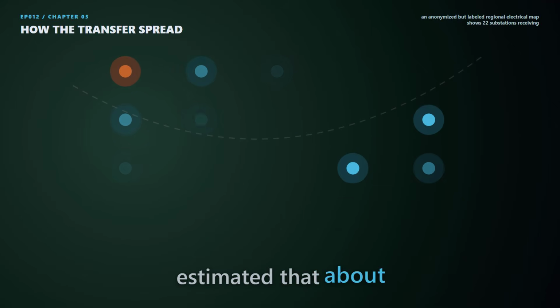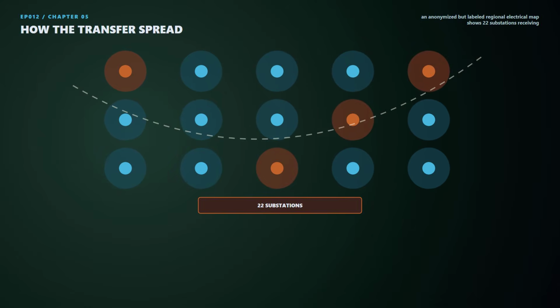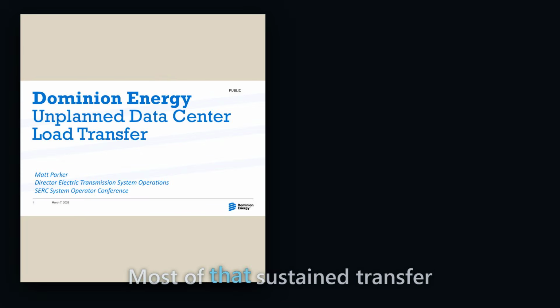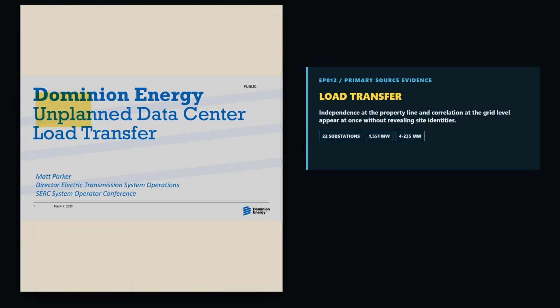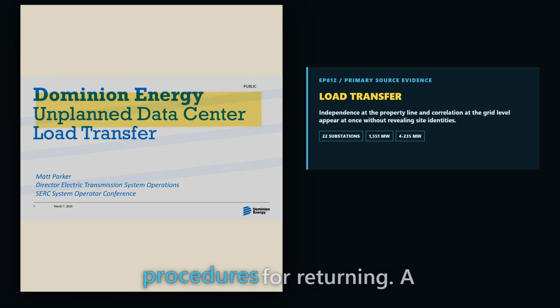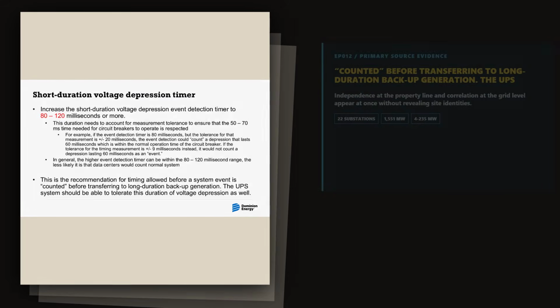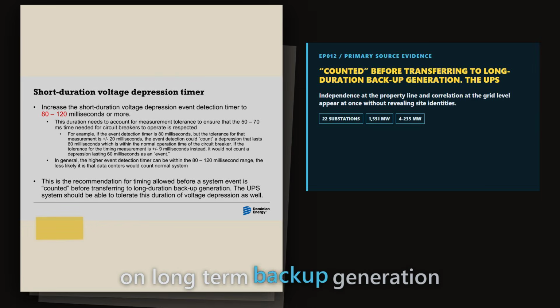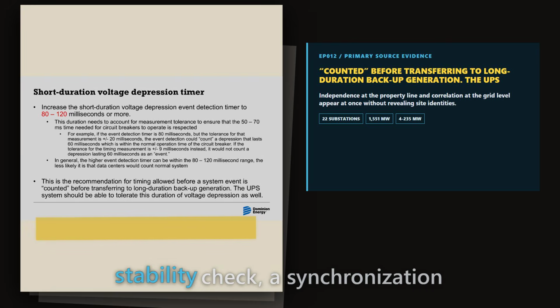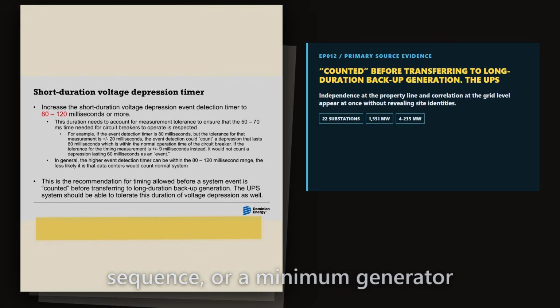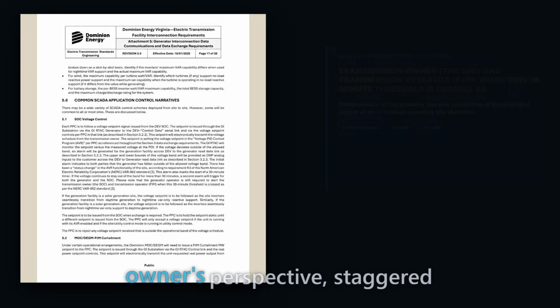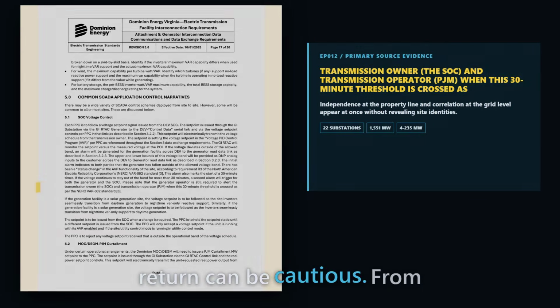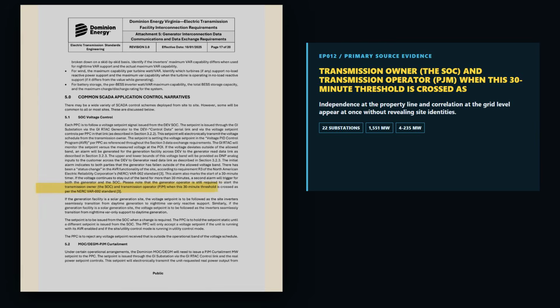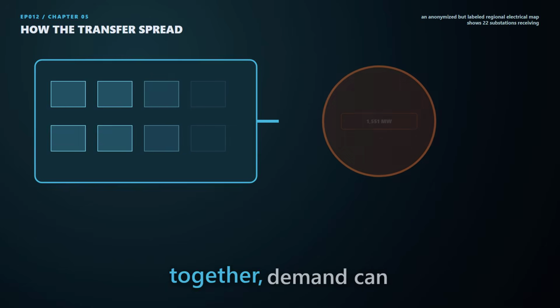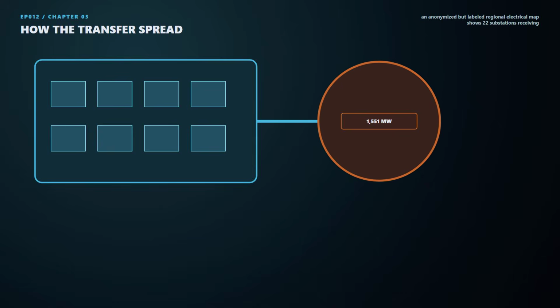NERC estimated that about 1,260 megawatts remained off the grid for hours. Most of that sustained transfer followed the third depression. Different operators then had different procedures for returning. A static UPS might settle back quickly. A facility on long-term backup generation might wait for personnel, a stability check, a synchronization sequence, or a minimum generator run. From the building owner's perspective, staggered return can be cautious. From the system operator's perspective, uncontrolled return creates another forecast problem. If hundreds of megawatts reconnect together, demand can jump up almost as quickly as it fell.